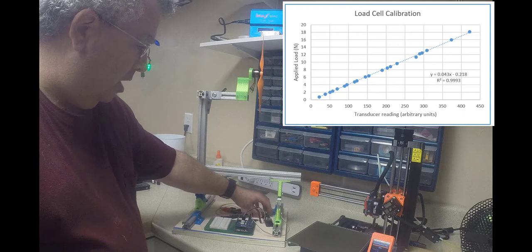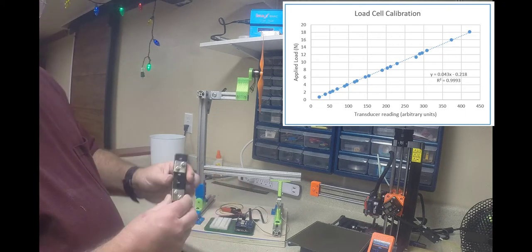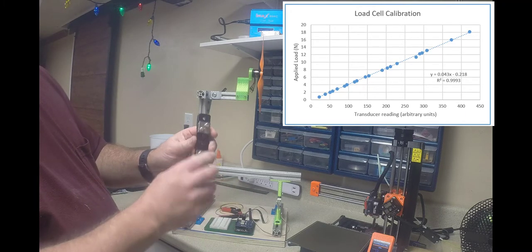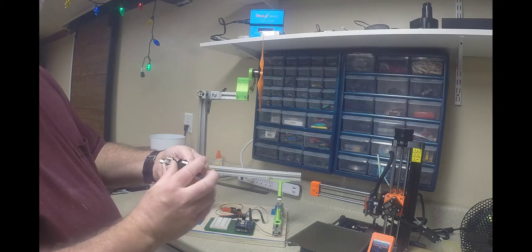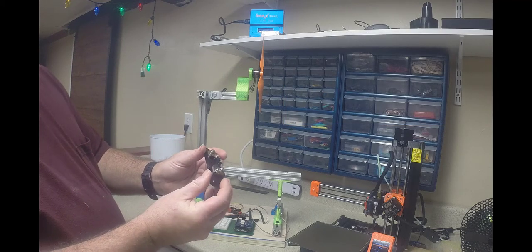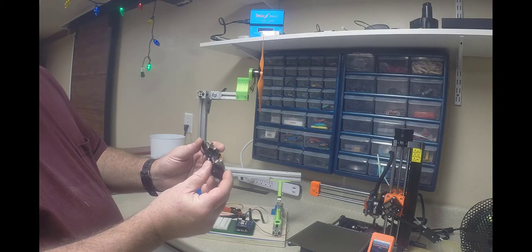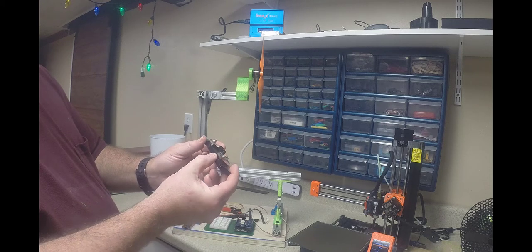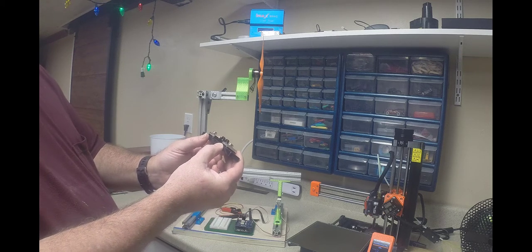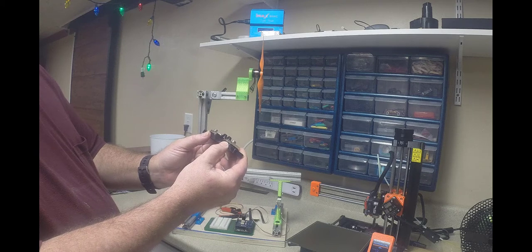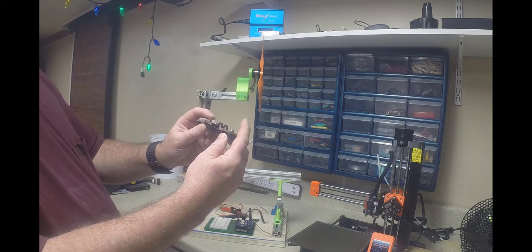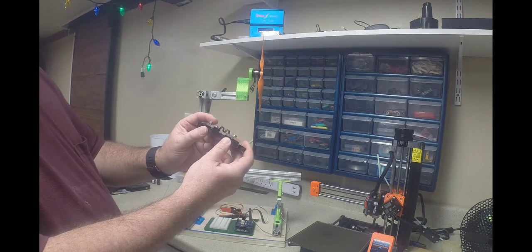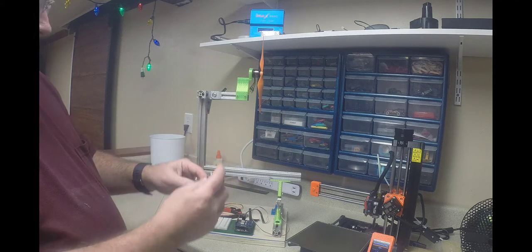The current from the motors that goes to the motor will be measured using this device. So this is a calibrated resistance shunt, and it has a full load of, at 10 amps, it would give a voltage across these two of 75 millivolts, or voltage change. So I'm going to be able to measure the voltage with that.